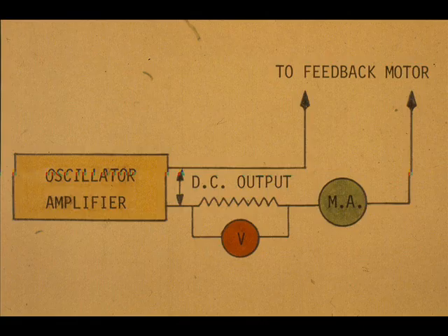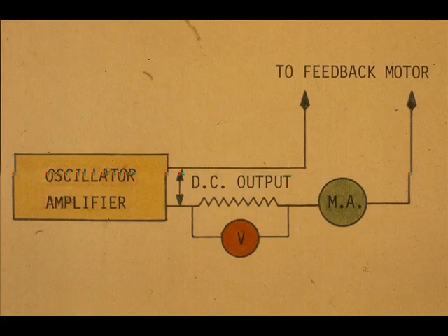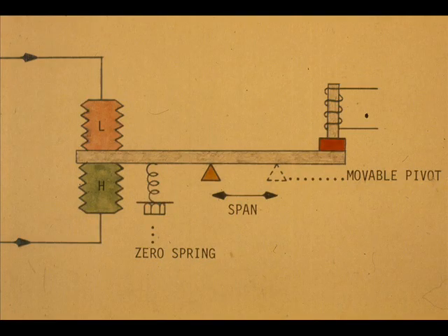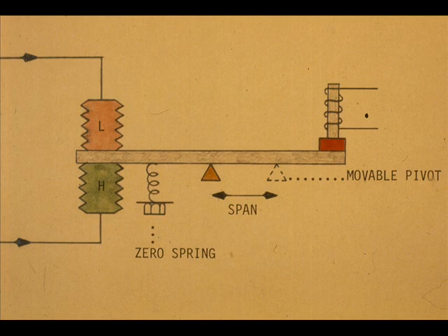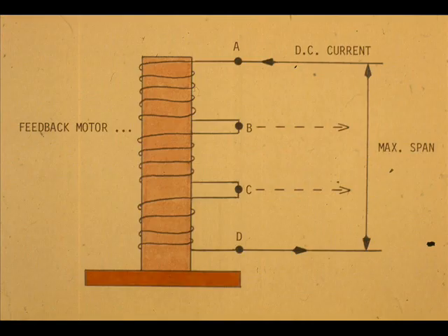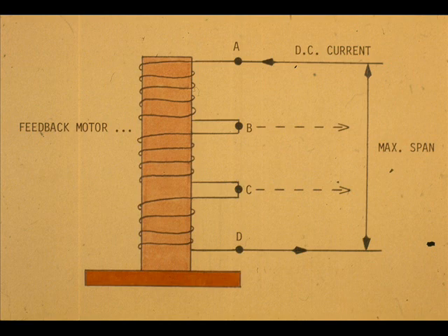The process input can be converted to either a voltage or current output value relative to the input. The zero and span adjustments are usually mechanical in the force balance type. In some models, span adjustment also requires an electrical adjustment. The DC output is connected across A and B for minimum, A and C for medium, and A and D for maximum spans.